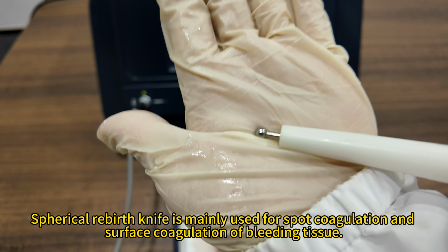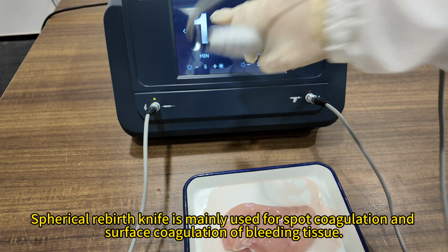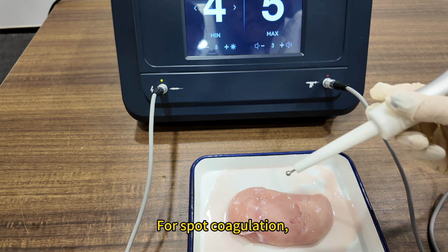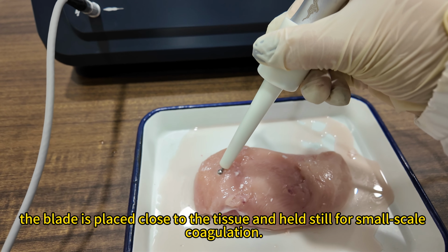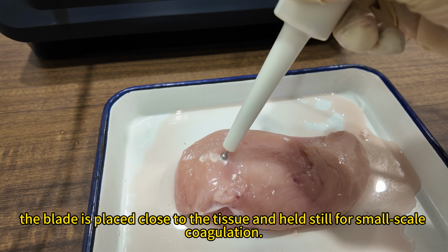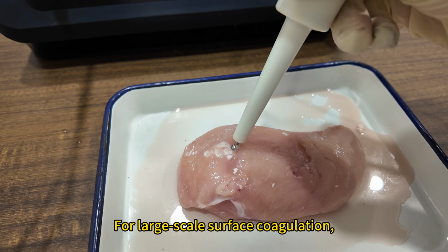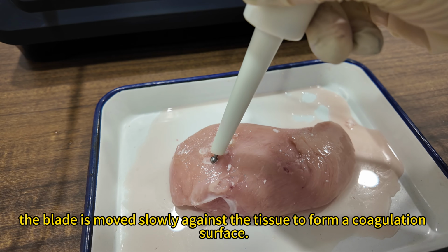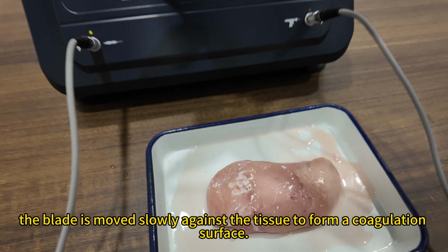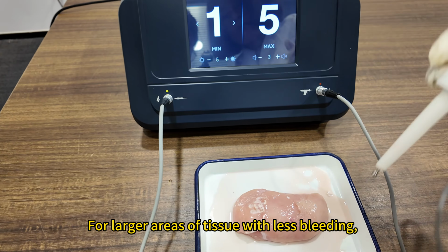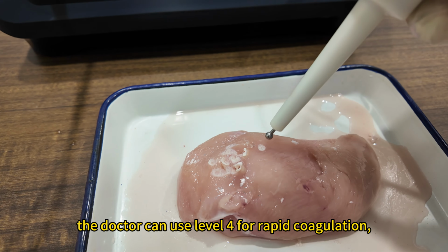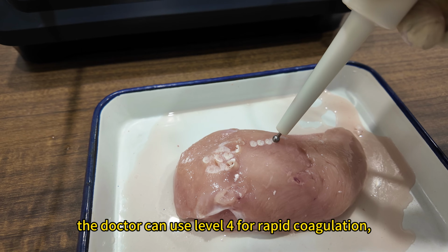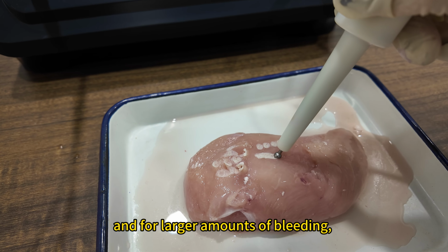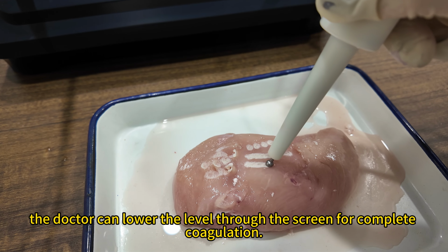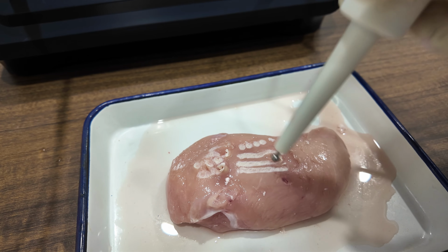The spherical rebirth knife is mainly used for spot coagulation and surface coagulation of bleeding tissue. For spot coagulation, the blade is placed close to the tissue and held still for small-scale coagulation. For large-scale surface coagulation, the blade is moved slowly against the tissue to form a coagulation surface. For larger areas of tissue with less bleeding, the doctor can use level 4 for rapid coagulation. For larger amounts of bleeding, the doctor can lower the level through the screen for complete coagulation. After the surgery, press the switch to shut down the machine.